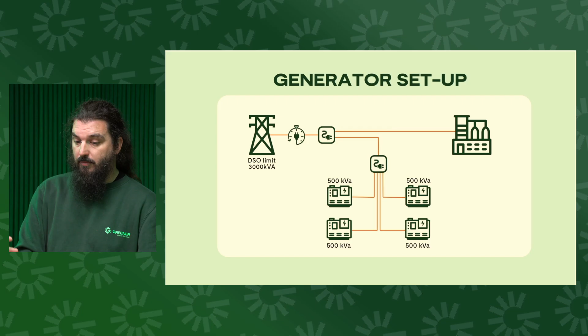And you can imagine that because the pressure goes up, they rent in some extra equipment, and that was a little bit too much for their connection. So if you look at what they did for the last couple of years before they talked to us, they put in 4 generators, 500 kVA, Stage 5, which had to run at between 50 and 80%. So the DSO limit on that connection to the distribution center was 3 MVA or 3,000 kVA, but they needed an additional 1 to 2 MVA of power.